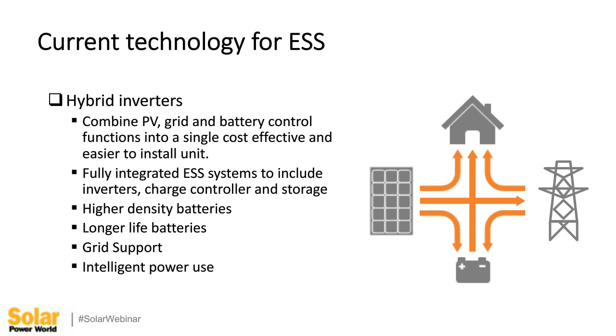We've got grid support, so hybrid inverters need to be able to support the new time of use, support lack of being able to feed in, manage the power that you've got, whether it's PV, whether it's batteries, wherever the source is coming from. It needs to look at the loads, the demands that you need, and then satisfy them the best way to do it. Sometimes that's forced on you by grid outages. Sometimes that's forced on you by cost of electricity. Sometimes it's cheaper to go at this time than that time from the batteries. And your hybrid inverter should be able to deal with that, thus the intelligent power use.